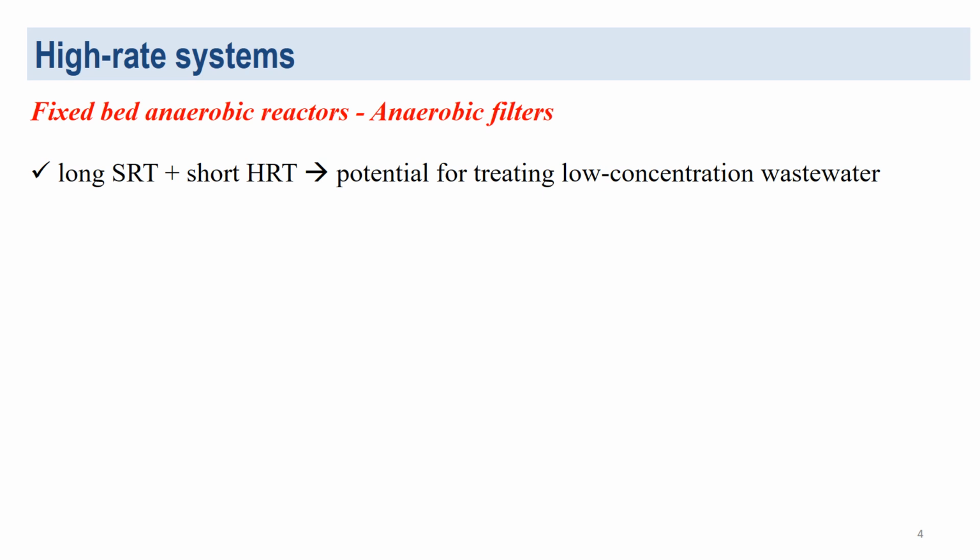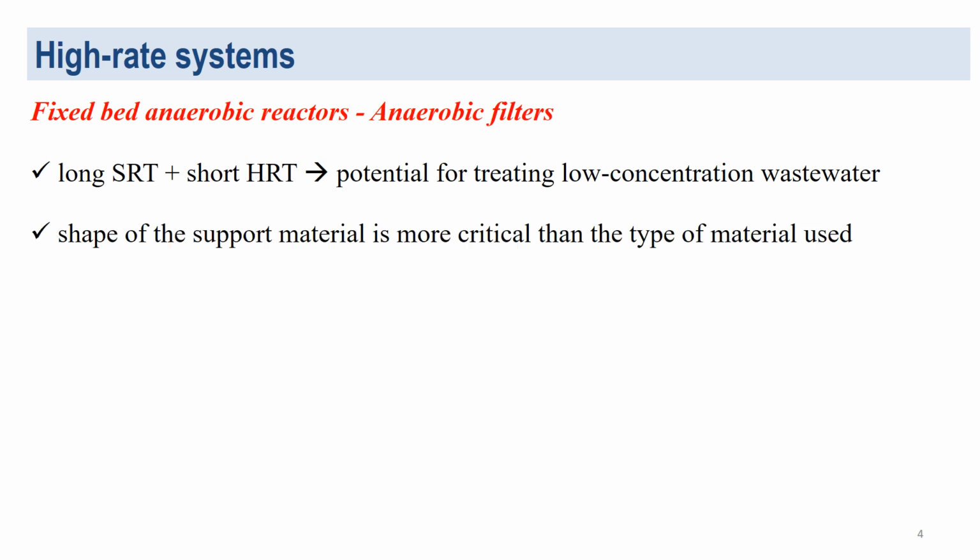The long solids residence times in the reactors, combined with the short hydraulic retention times, give the anaerobic filter significant potential for treating low-concentration wastewater. A large portion of biomass exists as suspended flocs, which are retained in the voids of the support medium, known as interstitial retention.